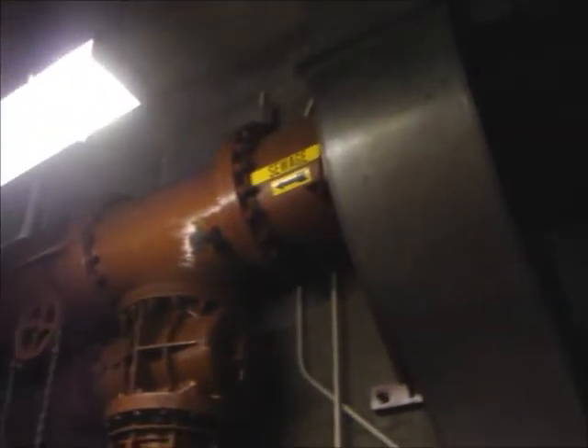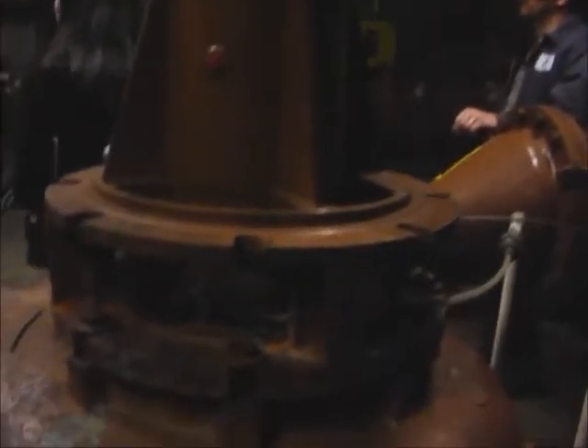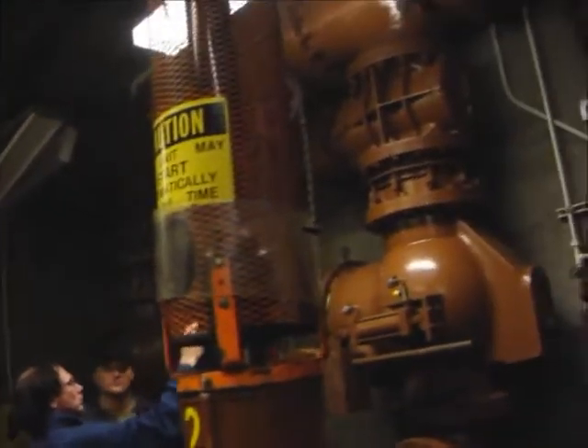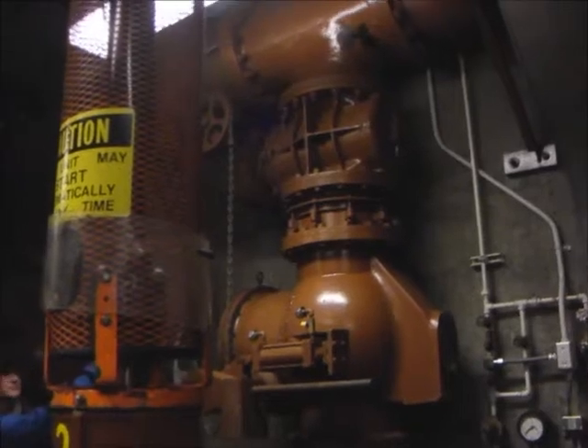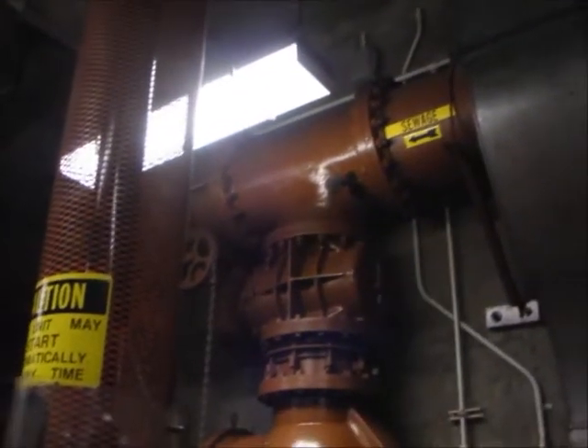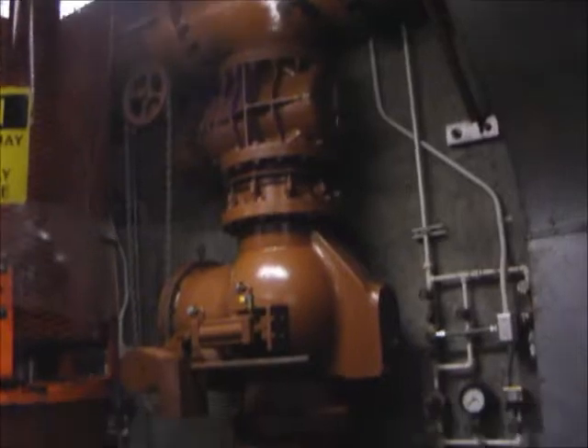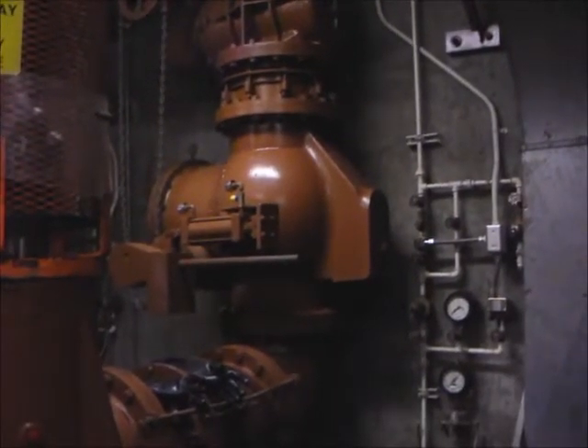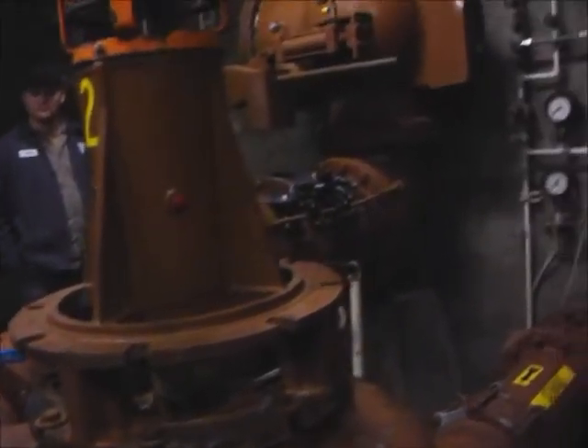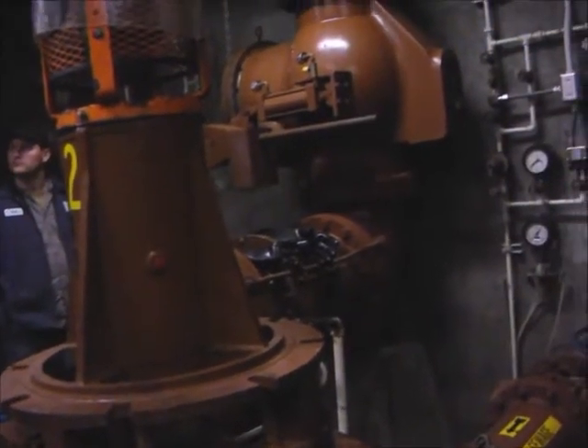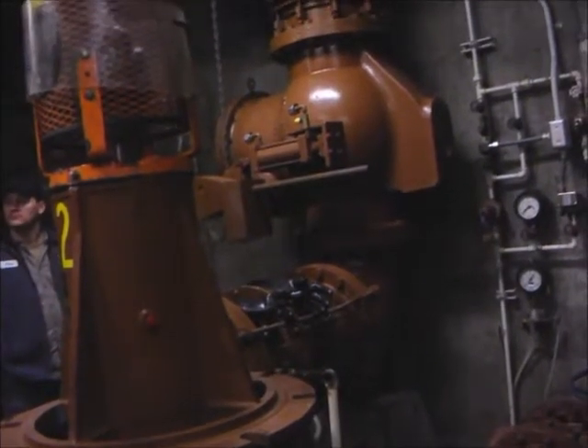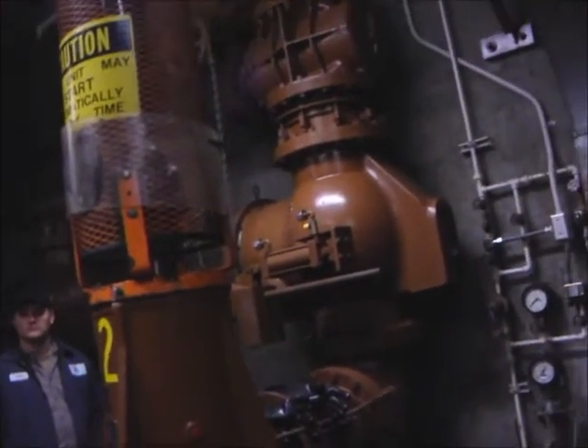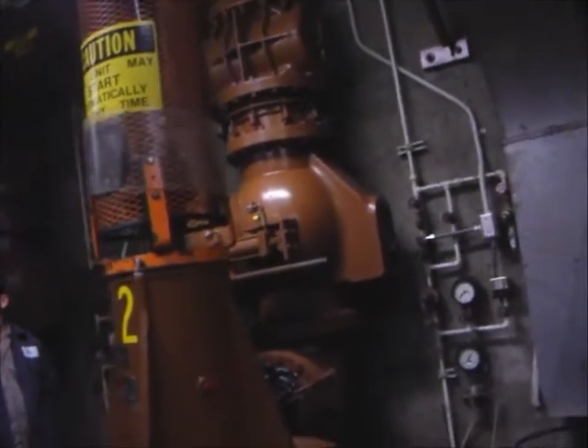You might want to straighten that out. I'll do that. That's just the way it is. You're not supposed to have T-sections. The short 90s they got with the suction on these pumps are bad. They got another short 90 around 45 right there, that's bad. The reduction is bad. The whole thing, in my opinion, needs to be done hydraulically and more efficiently on the pump station. No, it's what they had. I think when they built this, they had so much of this on the shelf.